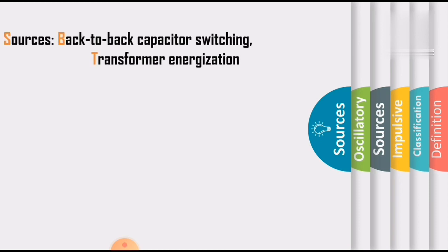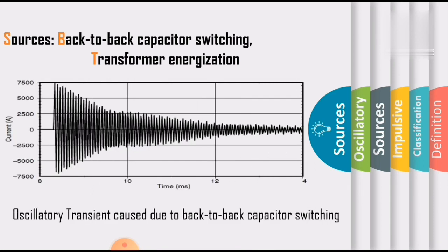The sources for oscillatory transients are back-to-back capacitor switching and transformer energization. This plot is a representation of the oscillatory transients due to back-to-back capacitor switching. On the x-axis we are considering time, and on the y-axis we are considering current. The obtained waveform for oscillatory transients due to back-to-back capacitor switching produces both positive and negative polarities — this section is positive and this section is negative.